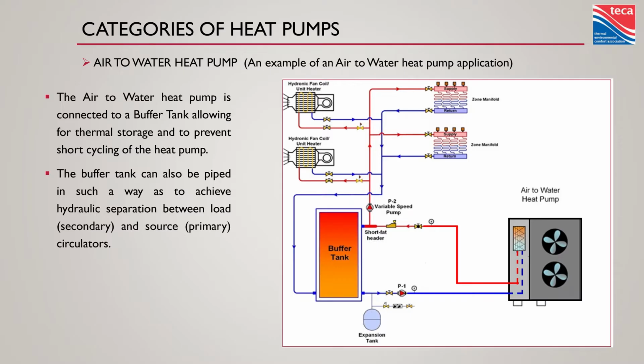This is different from a 4-port buffer tank configuration, because in a 4-port buffer tank configuration, you have to warm that tank before you can start transferring heat out to the load. That can be very devastating to a low mass heat emitter system, and even worse to a heat-cool system. Let me talk about some mistakes I learned the hard way. When someone turns on the air conditioning and hot air starts coming out of the fan coil because the buffer tank's still warm, you don't make friends.